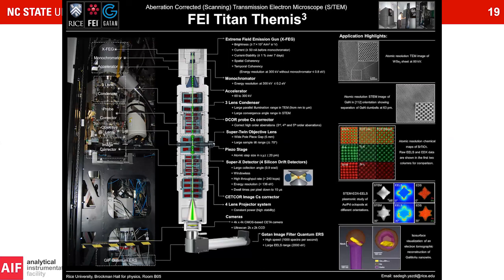A modern, fully-loaded TEM has quite a bit going on — though this diagram still misses about two-thirds of the components. There may be a monochromator for energy resolution, an electron source, an accelerator, a condenser lens stack, possibly an image corrector for the condenser lens, an objective lens where the sample sits, perhaps another image corrector, a projector system, an EELS spectrometer, and an EDS system. Not shown are the deflectors, scan coils, stigmators, and much else that make the microscope actually function.